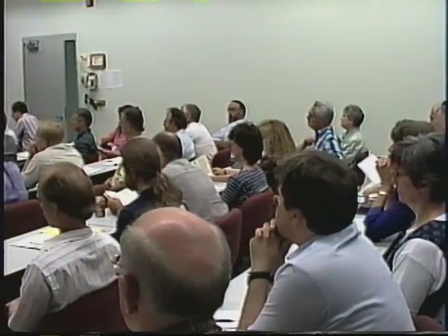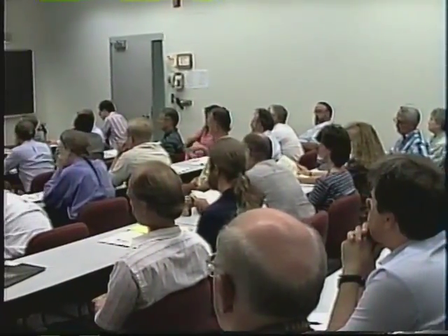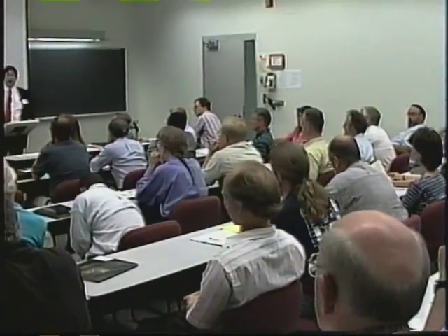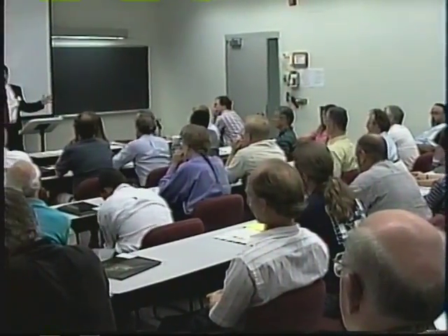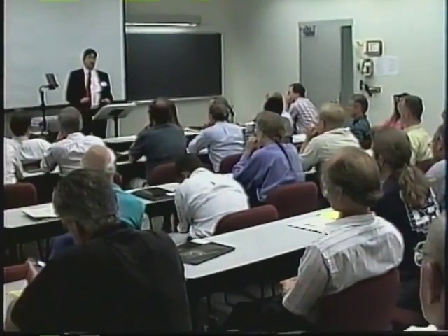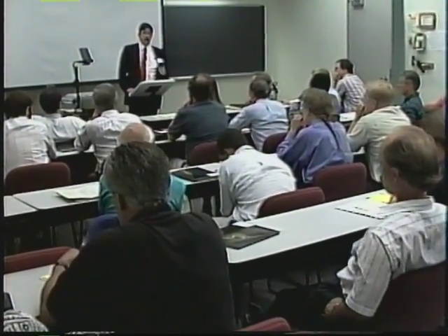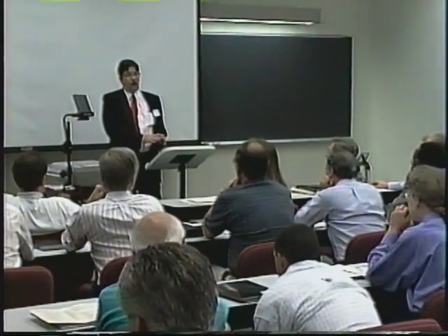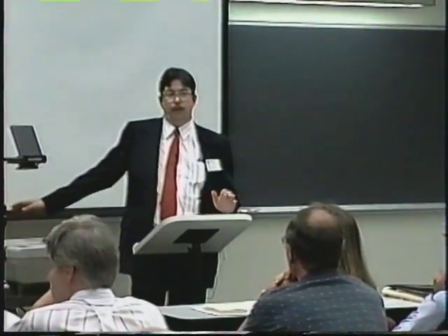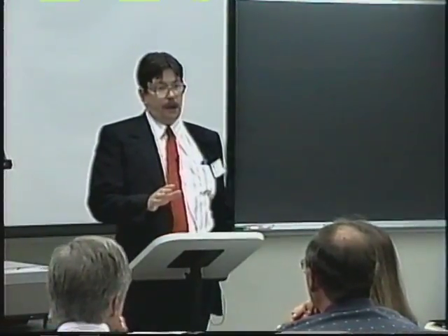And in fact, our paradigm within the laboratory now is you run your standards, you do a quick regression, you run 2 externals at the top and bottom end of your range, you calculate those externals, and if they're not within the control limits, you stop the process right there. So no sample gets run until there's been a demonstration of linearity and accuracy. Precision we don't worry about until the run's going on, but right off the bat, we're looking for the quality of the process before we even start to get into the samples. Did I answer your question?